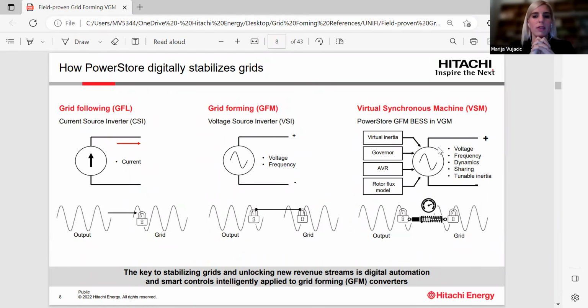To overcome that challenge, we added on top of grid forming voltage source inverters a virtual synchronous machine. This is the software solution which emulates the behavior of the synchronous generator. So the algorithm consists of 4 different blocks: frequency governor, virtual inertia, automatic voltage regulator, and rotor flux model, and provides or ensures a stable operation in parallel with other generators. What is also important to highlight here is the capability of the virtual synchronous machine grid forming to provide more than one service. So it can provide inertia, for example, when the battery energy storage system is discharging, and this is really when this value stacking comes into play.